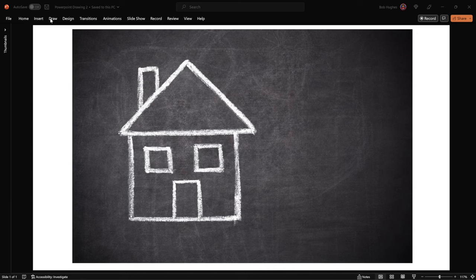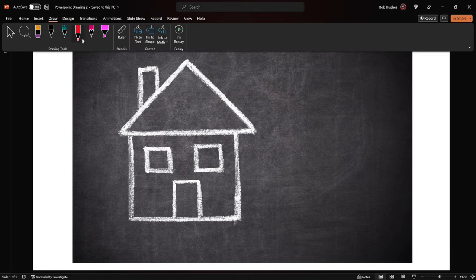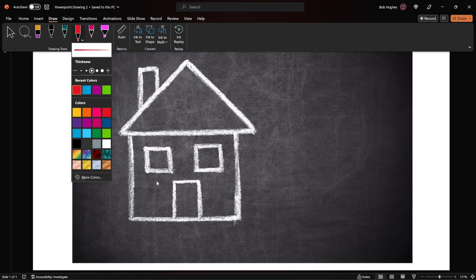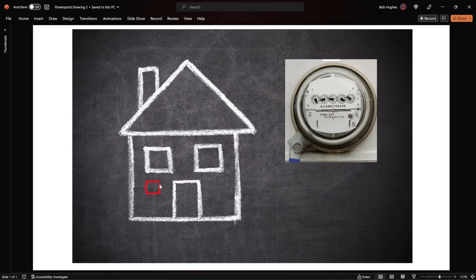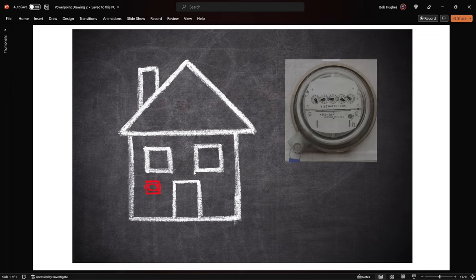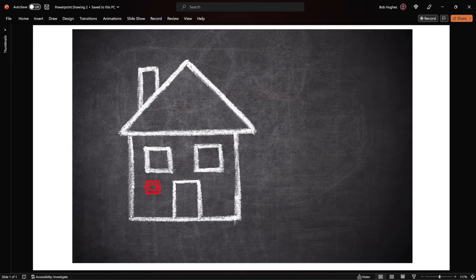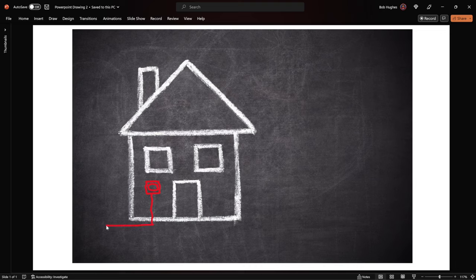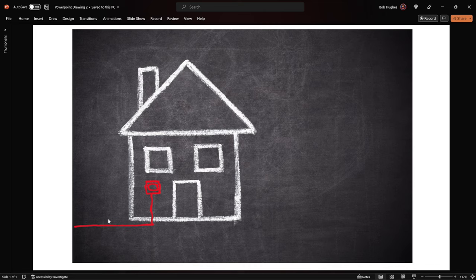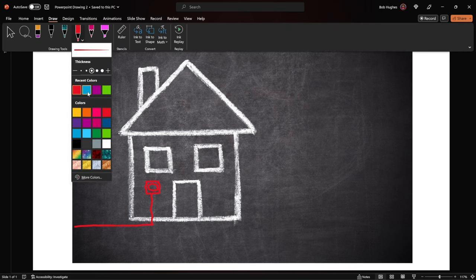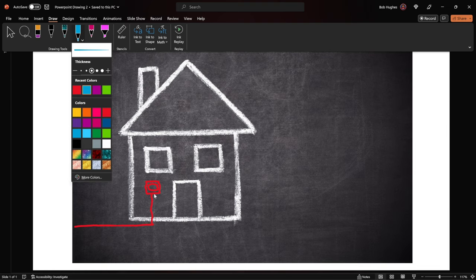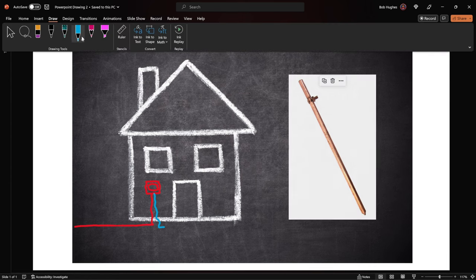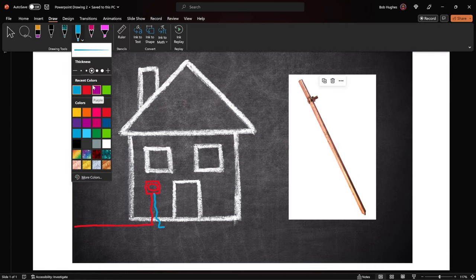Homes in the United States of America come with this wonderful square or rectangular metal box on the side or the front of the home with a glass globe that allows a person to come by one time per month and take a look at what's been going on, how much electricity has been consumed, and then there's usually some rather thick diameter conduit that goes down into the ground and then a large electric cable that's running to the utility provider that provides us and brings us our electricity. This also normally has some type of ground rod associated with it, and so somewhere in here there'll be a separate wire that will go down to the ground and it will attach to a ground rod. And that ground rod, at least by code here where I live, must be completely underground and must be eight feet long, solid copper or copper clad.